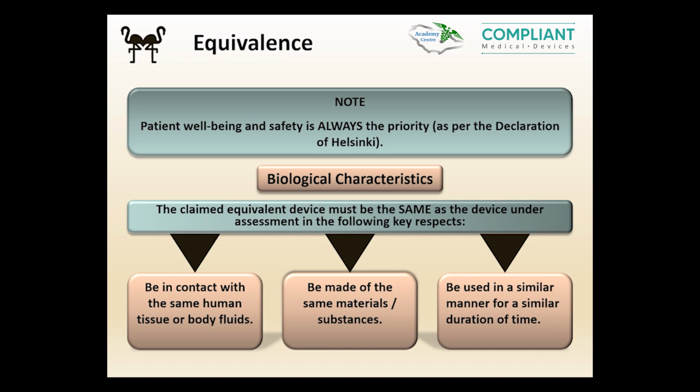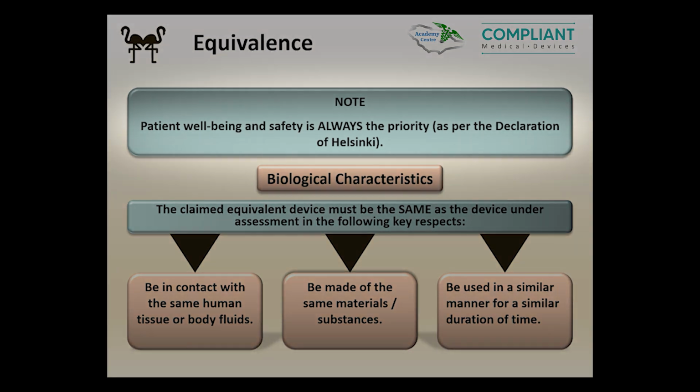Although clinical investigations are a very common way of gathering clinical data for a medical device, and one might think that running a clinical investigation is always a good thing to do, this is not quite the case. Clinical investigations are not risk-free. In a clinical investigation, we are often evaluating a medical device that is new or incorporates novel or untried materials or technologies. Because under the regulation, patient safety and well-being is always paramount, we only want to run a clinical investigation when it is unavoidable.